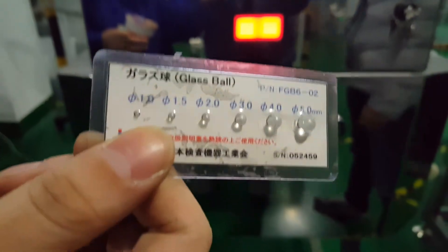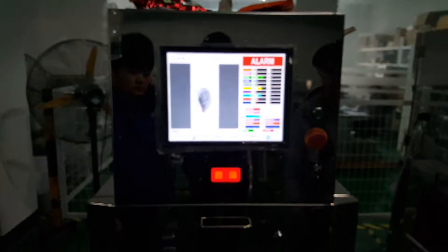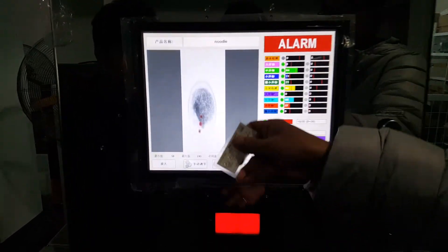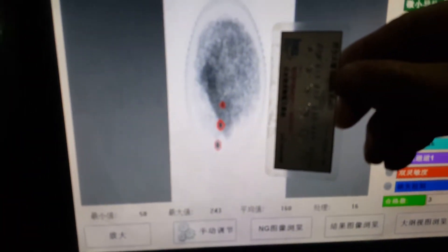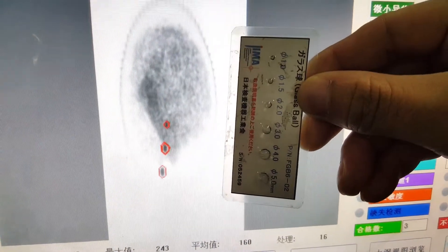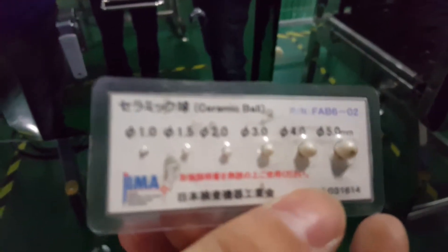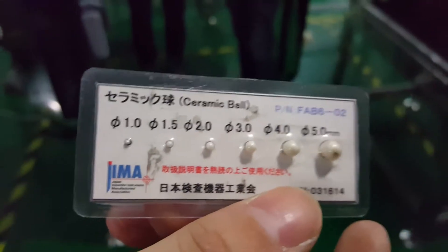First, we put the glass ball on top of the product and pass it through the X-ray tunnel again. We hear alarms and we can see the X-ray machine picked three red points, which means the best sensitivity for the glass ball is 3.0 millimeters.